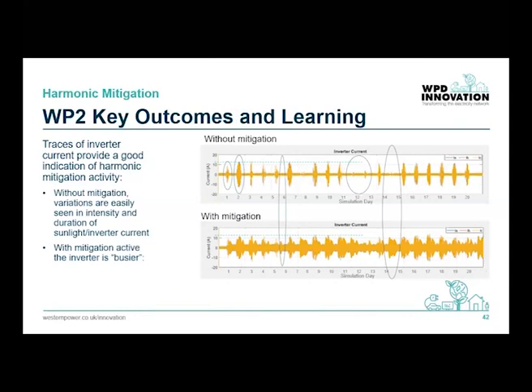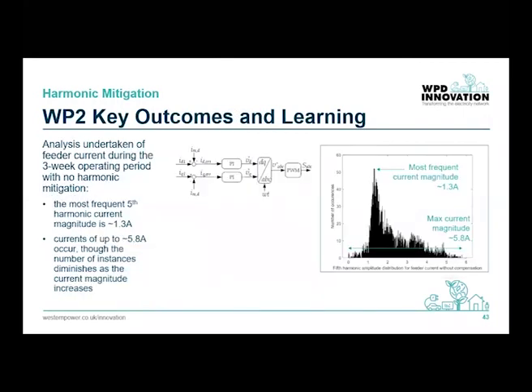So let's set about quantifying the impact of the harmonic controller. If we look at some analysis of feeder current over the 3-week period, we see a range of harmonic current magnitudes. For the 5th order harmonic shown in this chart, we see that the most frequent magnitude was around 1.3 amps and the maximum current was around 5.8 amps.